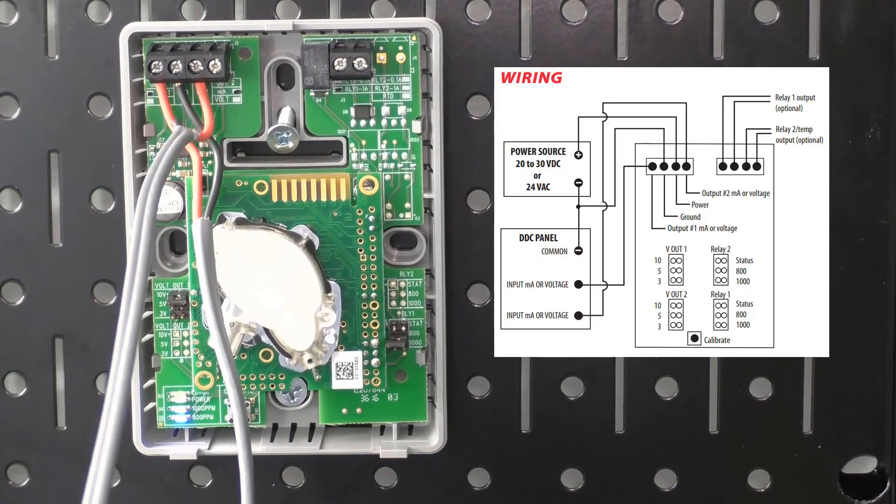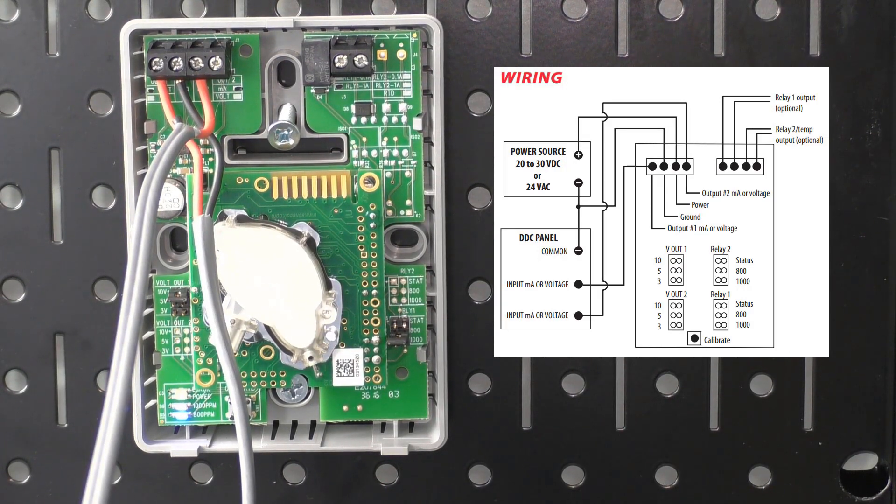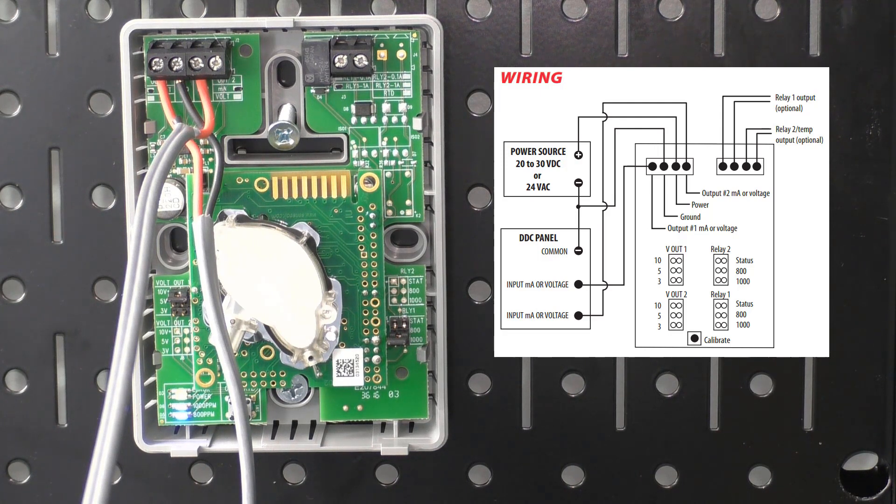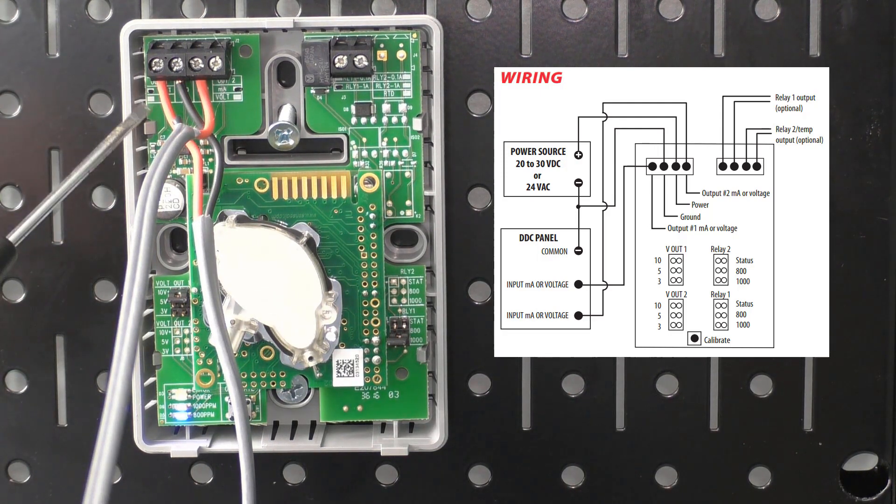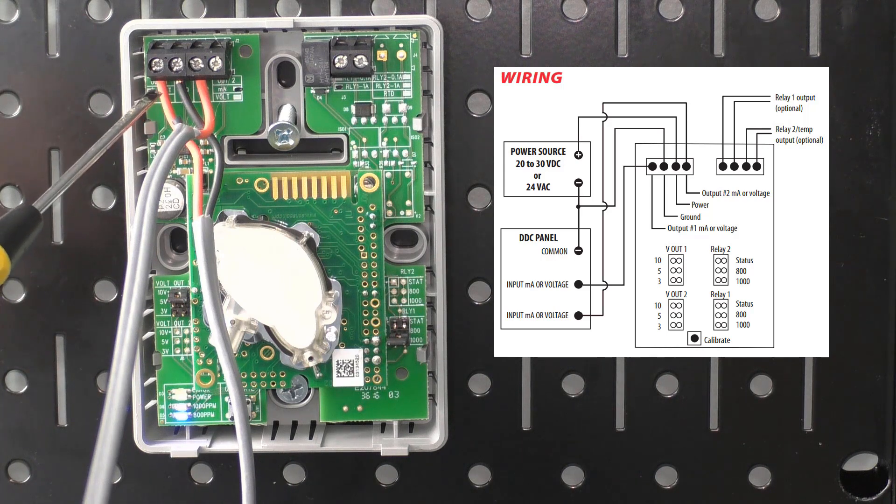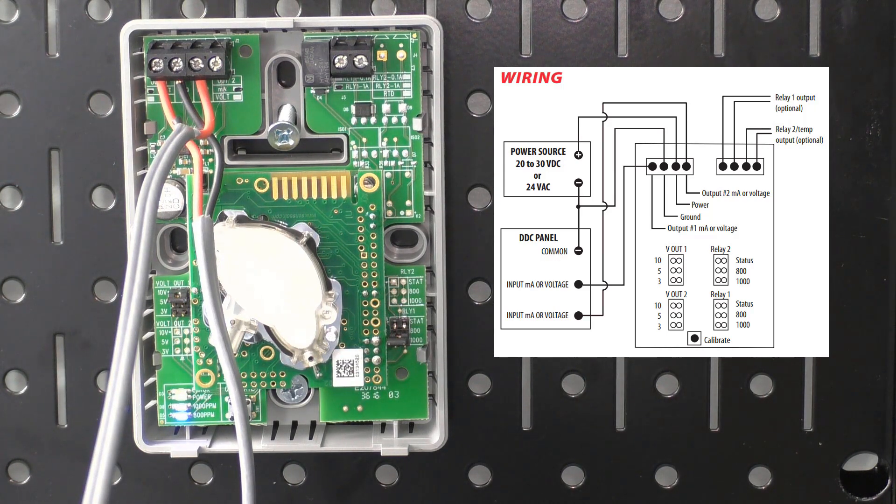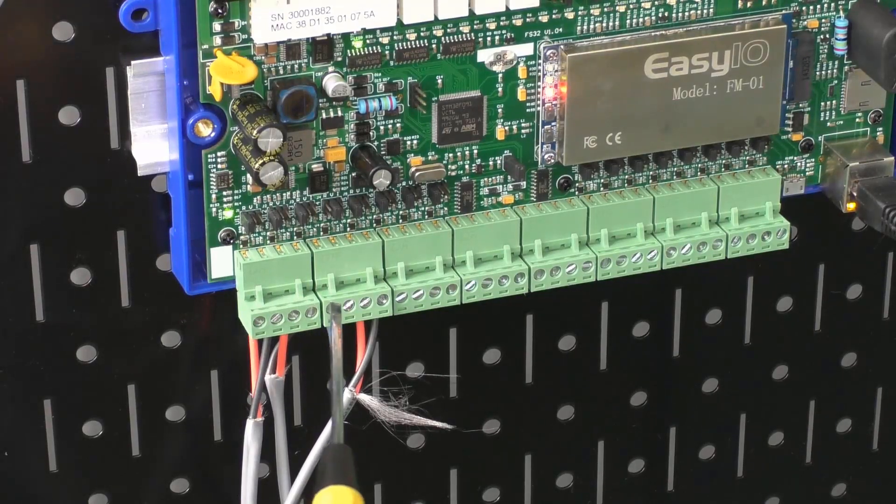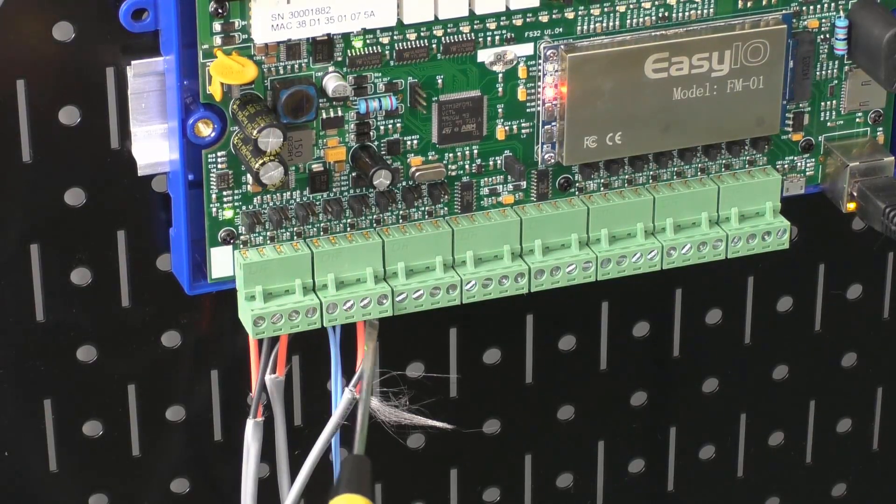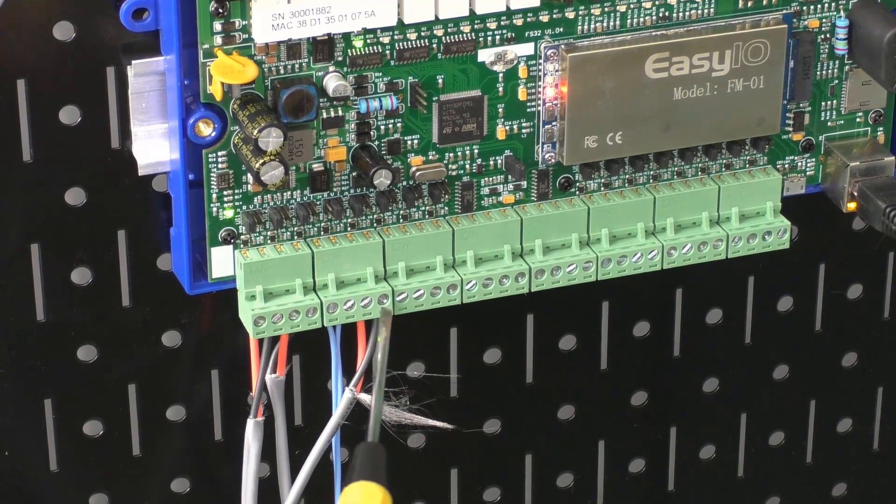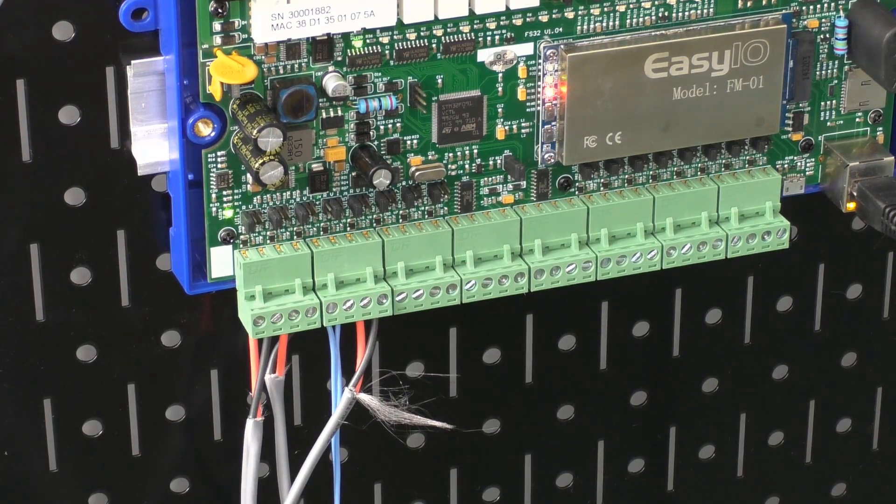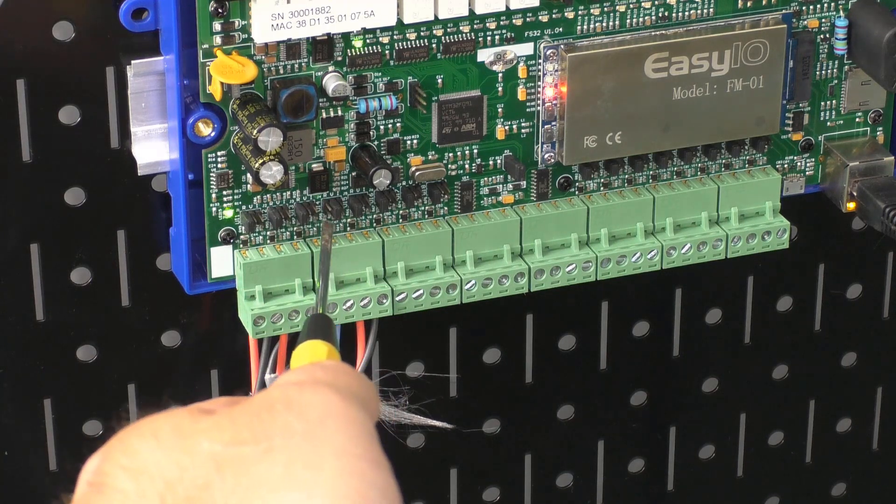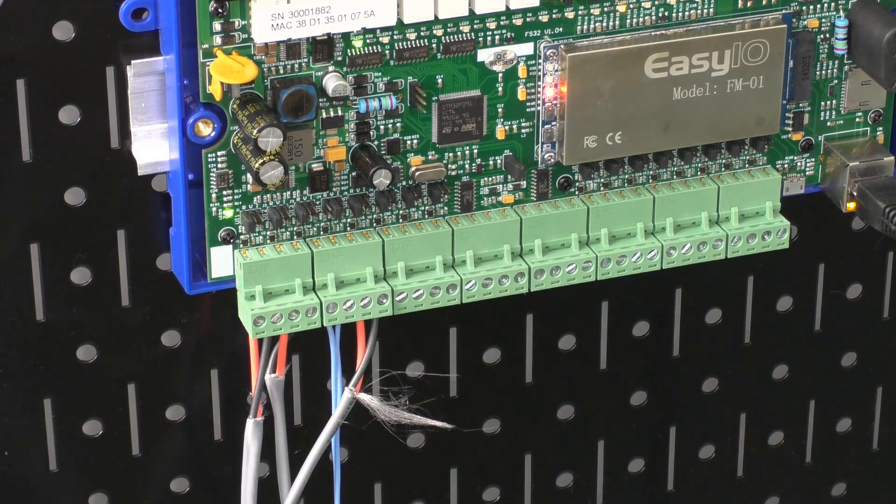Then we can see that we have our common and our input, common being black, input being red. We can see that on our controller those are wired to the input and input common on our actual controller. Here we see our hot input right here and our common system right there. We can also see that we have our jumper set to voltage.